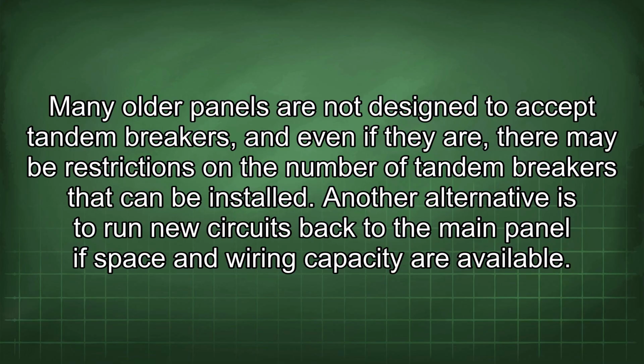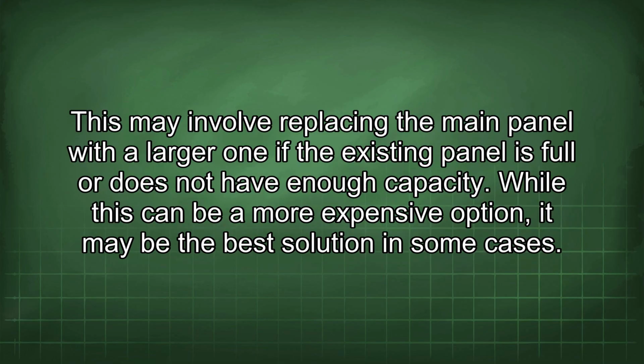Another alternative is to run new circuits back to the main panel if space and wiring capacity are available. This may involve replacing the main panel with a larger one if the existing panel is full or does not have enough capacity. While this can be a more expensive option, it may be the best solution in some cases.